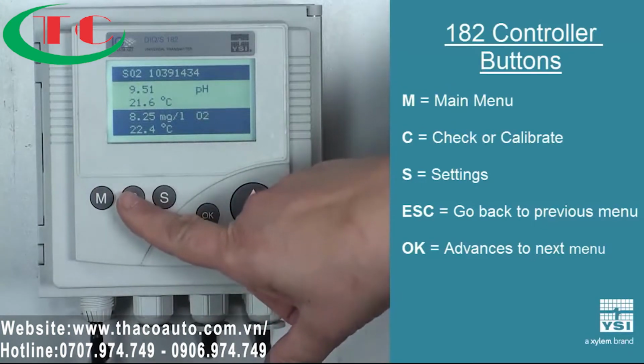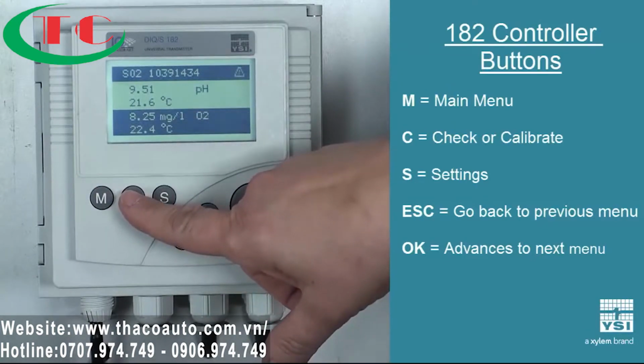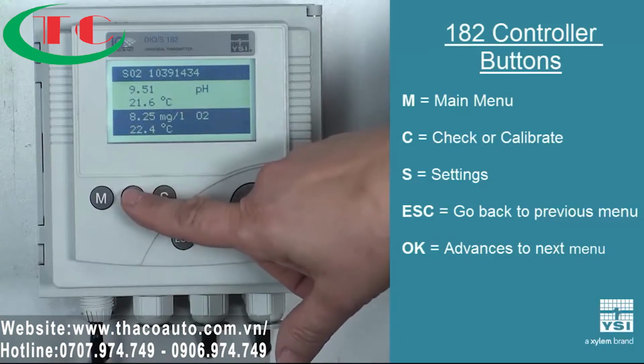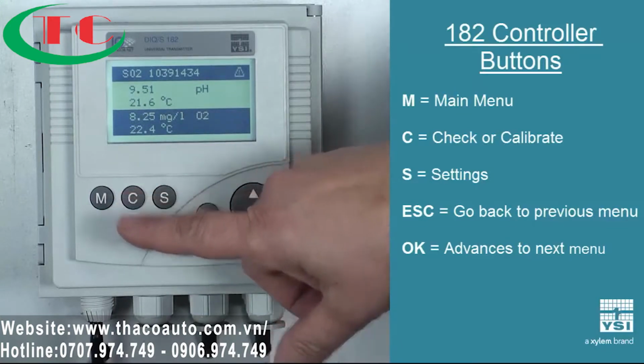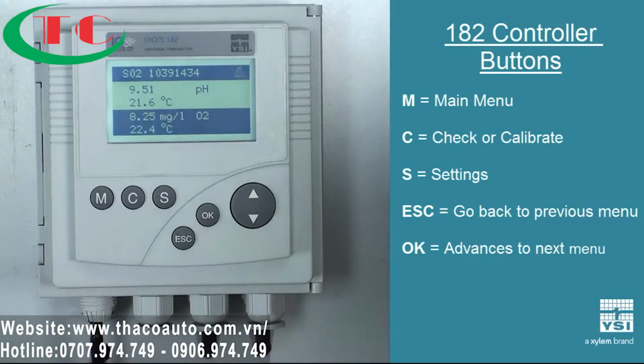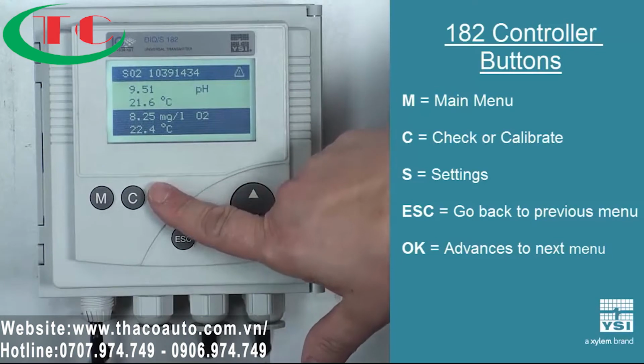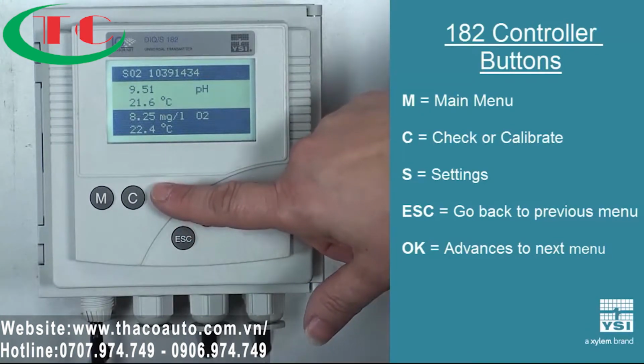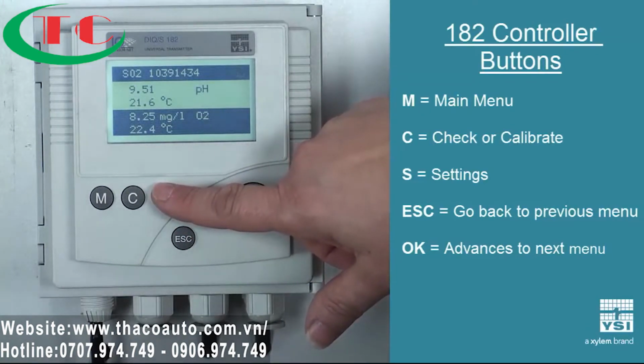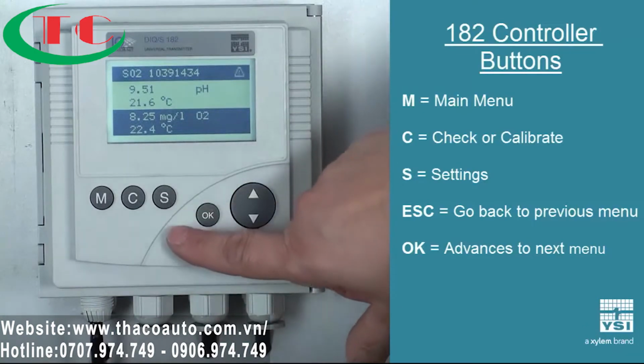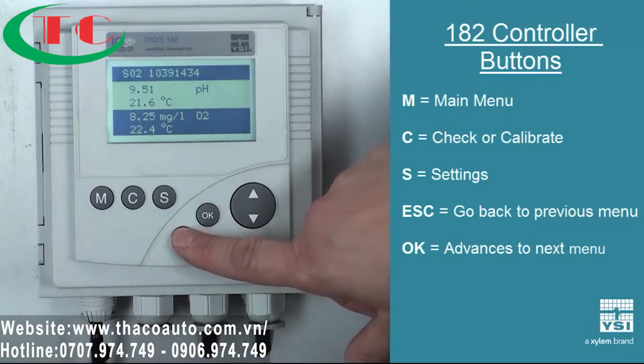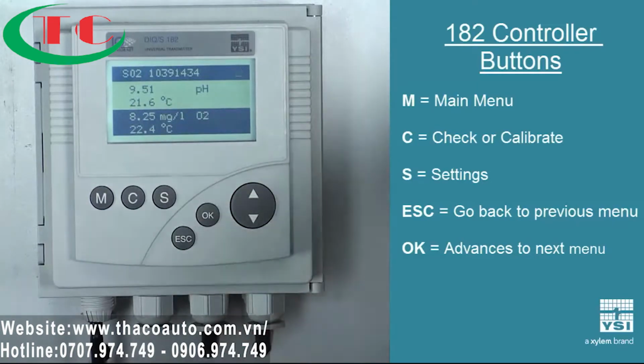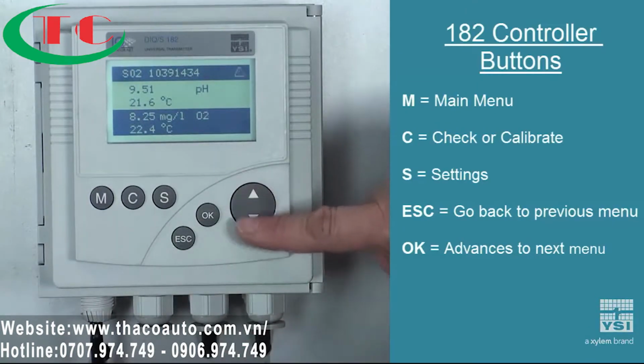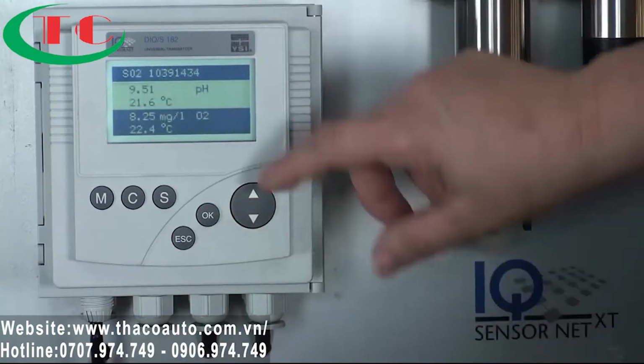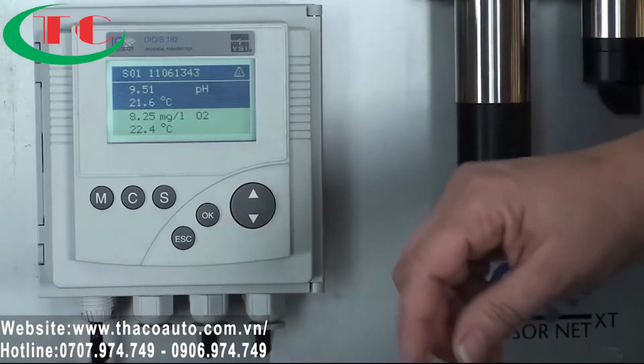The C button I like to think of as check or calibrate or a matrix adjustment. So that's where you're going to go in and do any kind of calibrations to a sensor, or check your sensor, or do a matrix adjustment. Your S button will take you into a settings menu where you can set up outputs and links. The escape button will take you back one menu, and the OK button is going to advance one menu. Your up and down arrow keys are just going to help you maneuver through the screens.